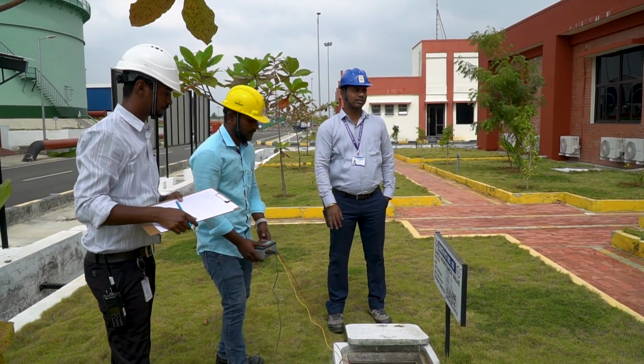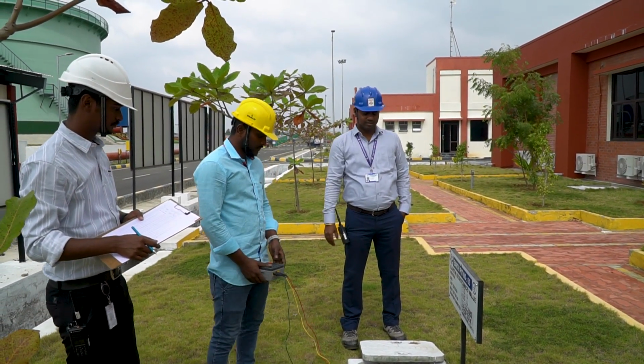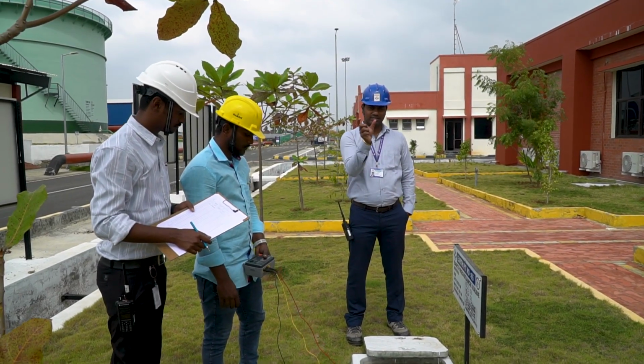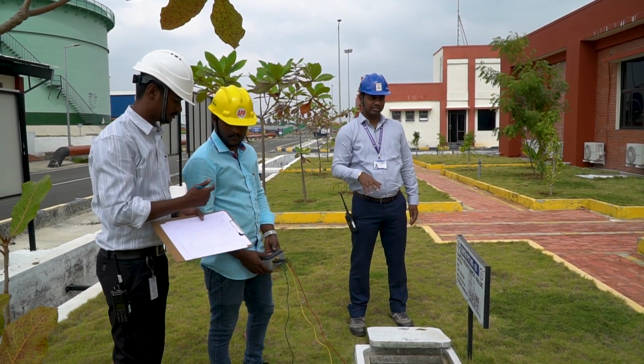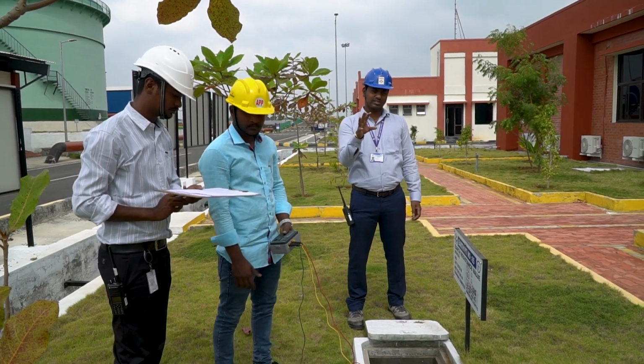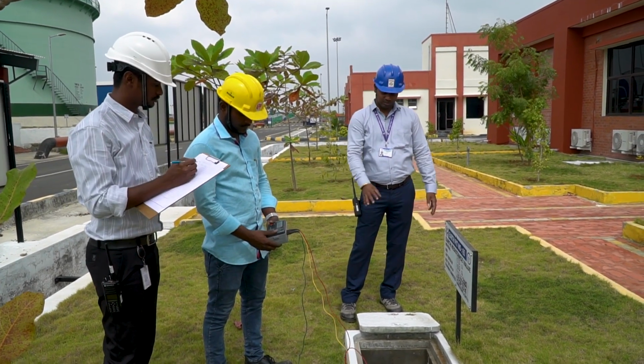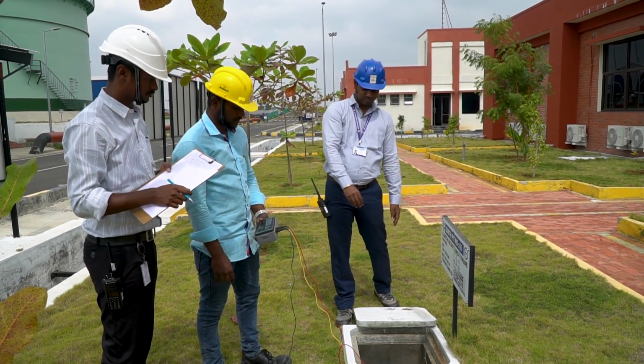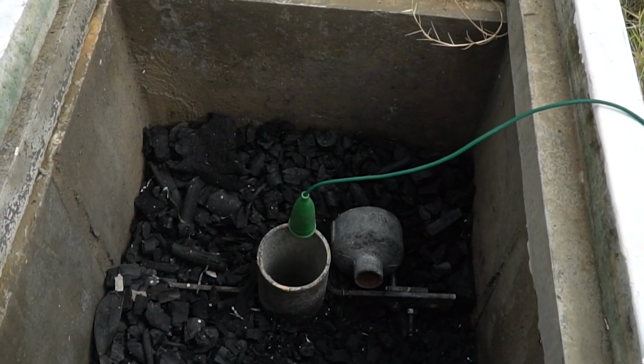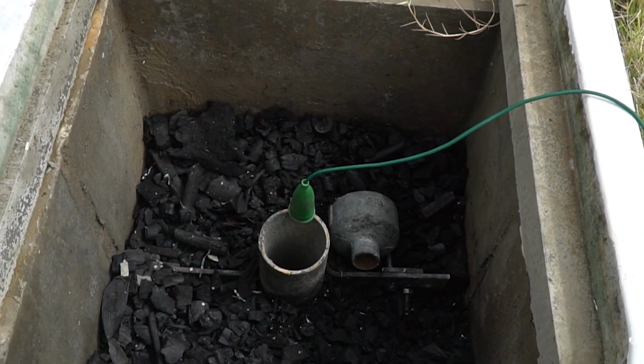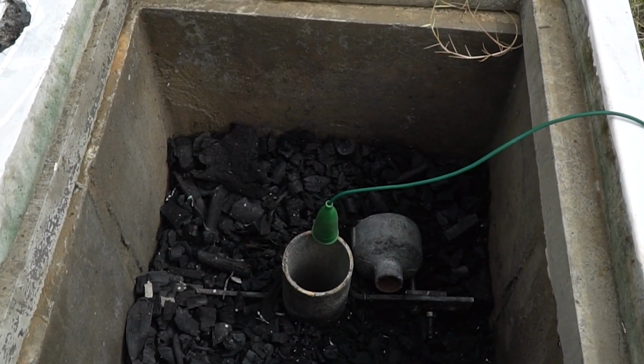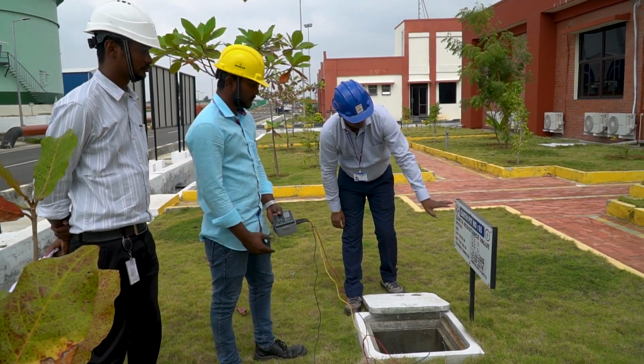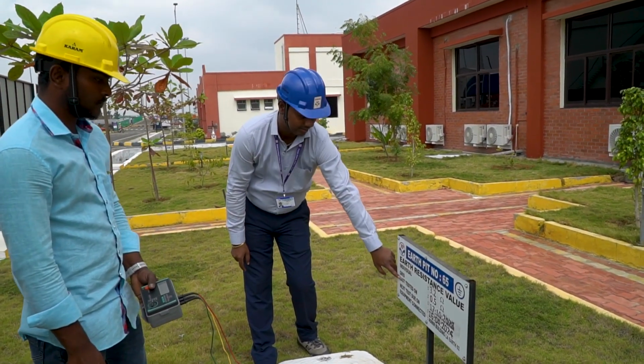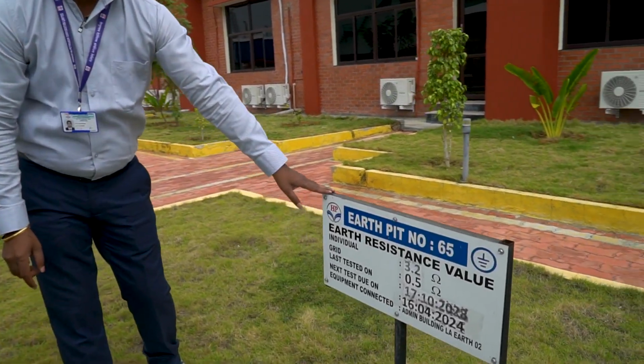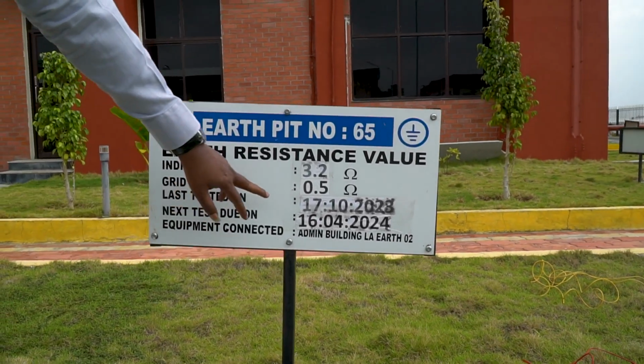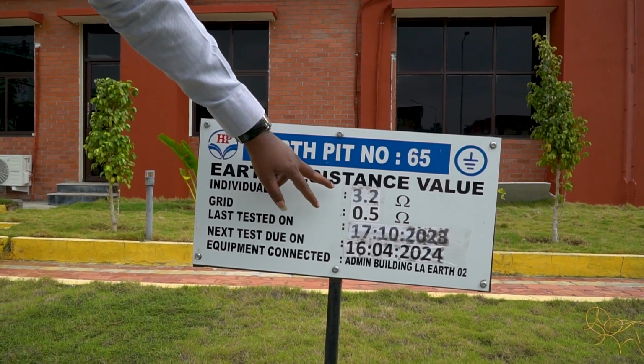This is one of the earth pits connected to your building lightning arrestor. This earth pit should have a desired standard value, then only it is accepted. So we are checking what that value is presently. We have already done conditioning. We have put charcoal and watered it. You can see inside. Previously we checked this earth pit and noted down the values. These values are accepted. The last checked date is mentioned, and when this earth pit needs to be checked again is also mentioned. So this earth pit has acceptable values.